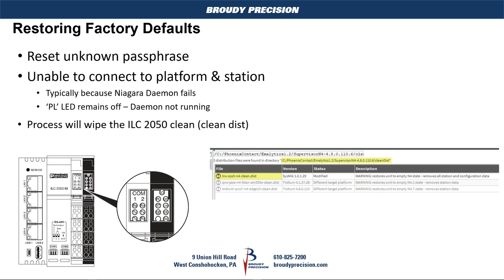If you don't know your passphrase or are unable to connect to your ILC 2050 — for example, you can't get to the platform, and if you can't get to the platform you're not going to get the station on the ILC — there are troubleshooting LEDs. One specific one, the PL LED, shows that the daemons are running and how loaded they are. If that LED is turned off it means the daemons are not running and you will not be able to access the platform. If you get into that position, you'll most likely need to do a wipe or factory restore using the clean distribution file.